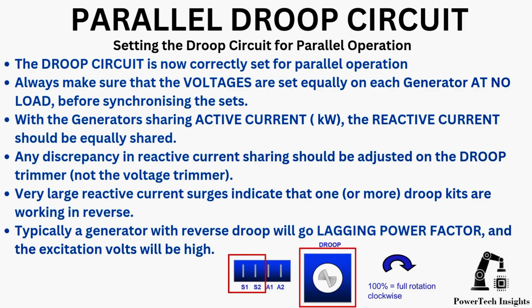Setting the droop circuit for parallel operation — the droop circuit is now correctly set for parallel operation. Always make sure that the voltages are set equally on each generator at no load before synchronizing the sets. With the generator sharing active current, the reactive current should be equally shared. Any discrepancy in reactive current sharing should be adjusted on the droop trimmer, not the voltage trimmer. Very large reactive current surges indicate that one or more droop kits are working in reverse. Typically, a generator with reverse droop will go to lagging power factor and the excitation volts will be high.